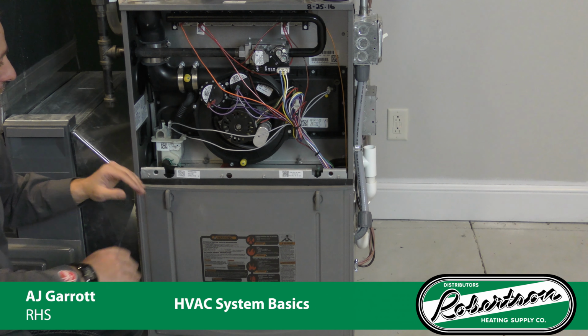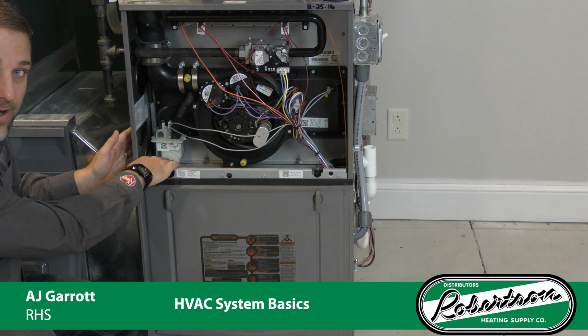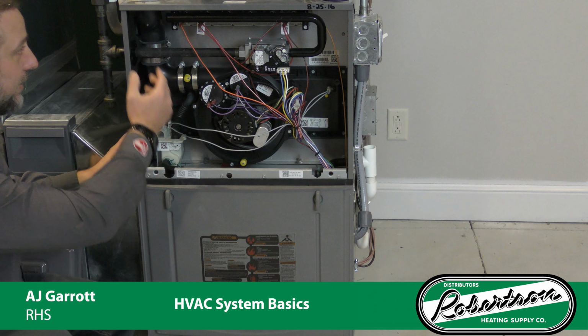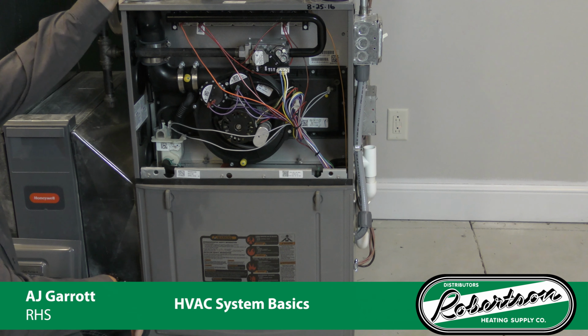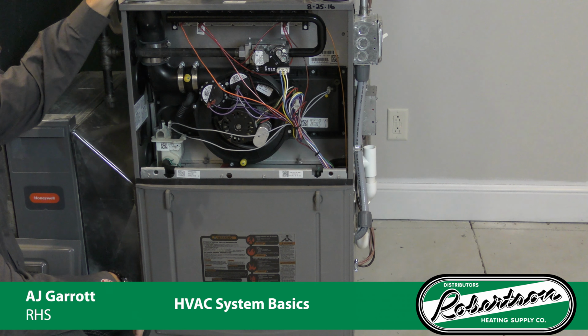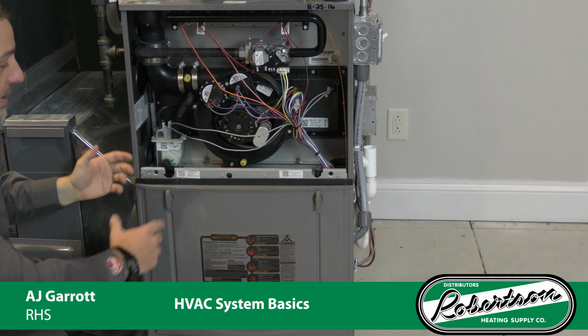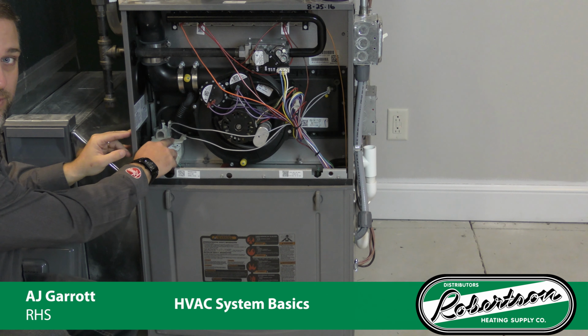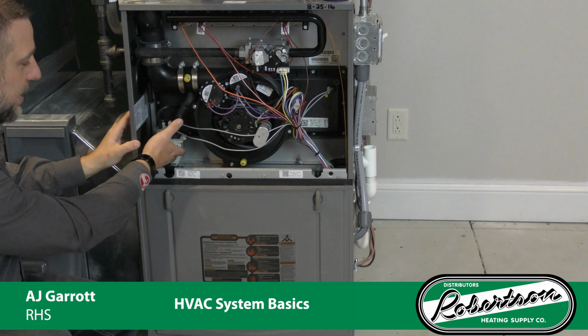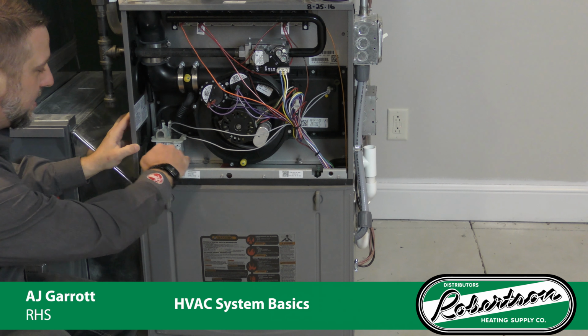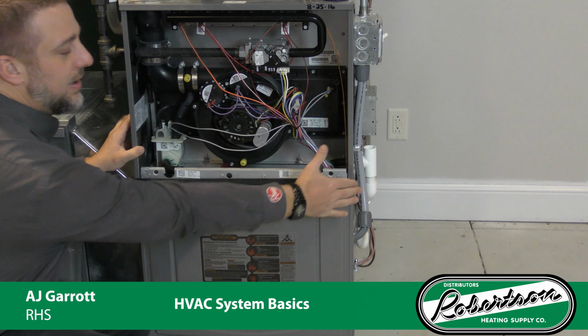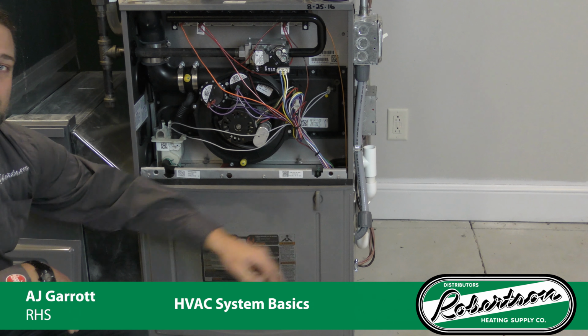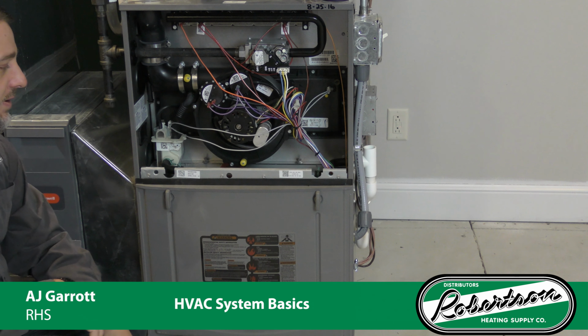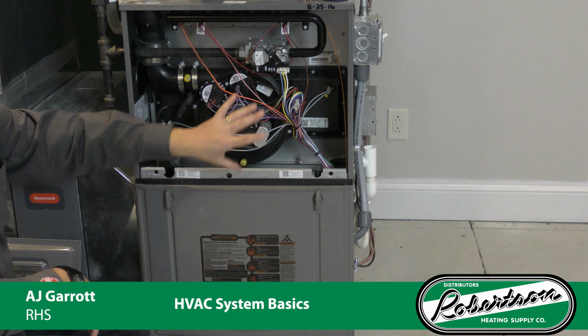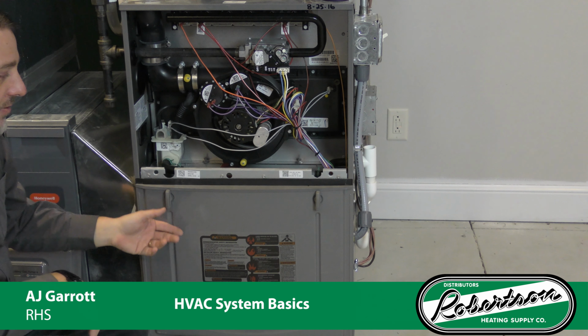We also have a condensate drain on this furnace down here. So we talked about how we have condensate coming out of the exhaust and we need to drain it out properly. This is what the trap is for. So the condensate trap holds a little bit of condensate in it, which then takes it out the pipe and out this side into our PVC pipe on that side of the furnace. That's pretty much what's happening up here in the gas furnace.